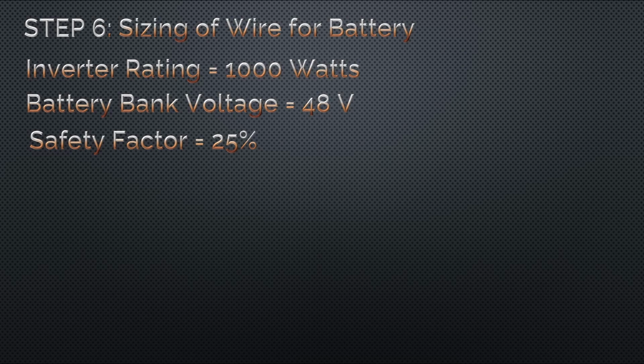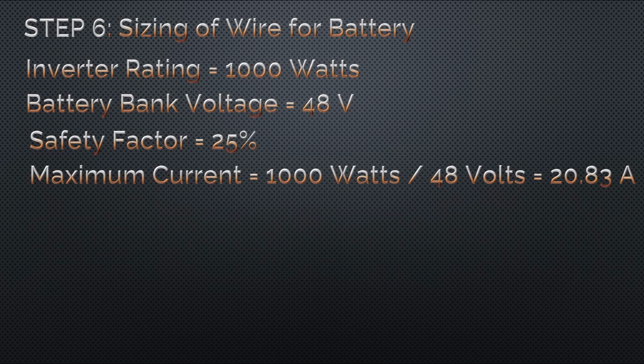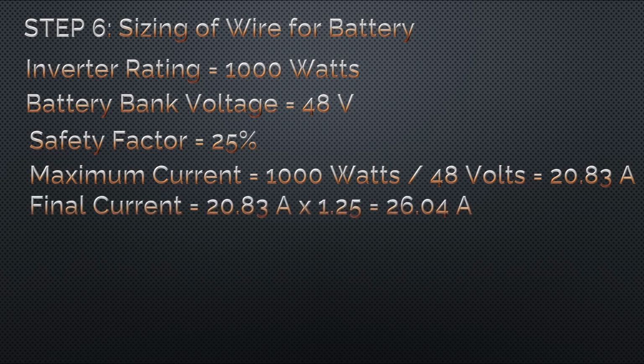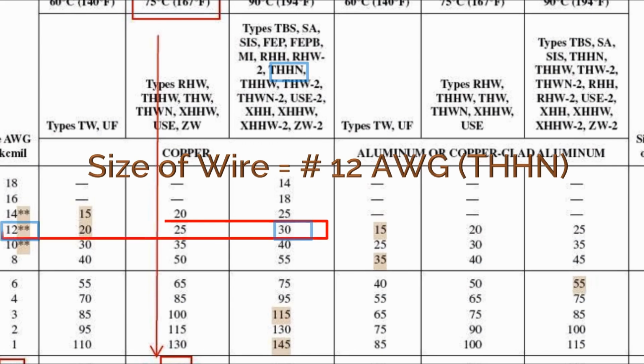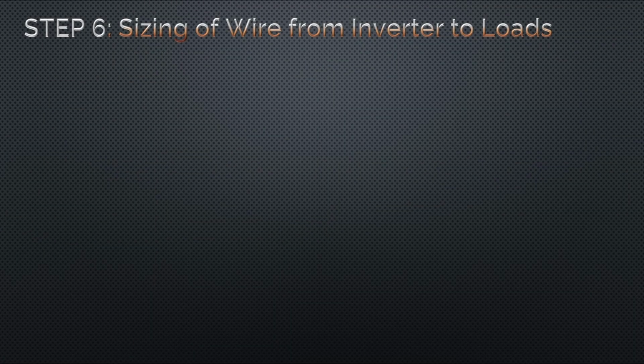Ngayon, kunin muna natin ang maximum current, and this will be equal to 20.83 amperes. Then apply the 25% factor and we will get 26.04 amperes. Now if we look in the ampacity table, we will use number 12 AWG THHN with 30 amperes full load current rating. So step 6 pa rin tayo, pero ang i-compute naman natin ay size of feeder wire from inverter to loads.